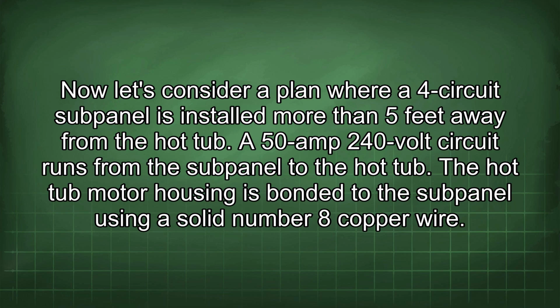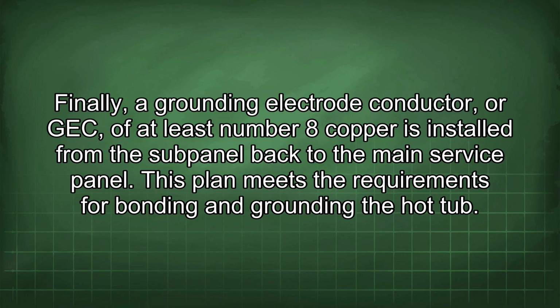Now let's consider a plan where a 4-circuit subpanel is installed more than 5 feet away from the hot tub. A 50-amp 240-volt circuit runs from the subpanel to the hot tub. The hot tub motor housing is bonded to the subpanel using a solid number 8 copper wire. Finally, a grounding electrode conductor, or GEC, of at least number 8 copper is installed from the subpanel back to the main service panel. This plan meets the requirements for bonding and grounding the hot tub.